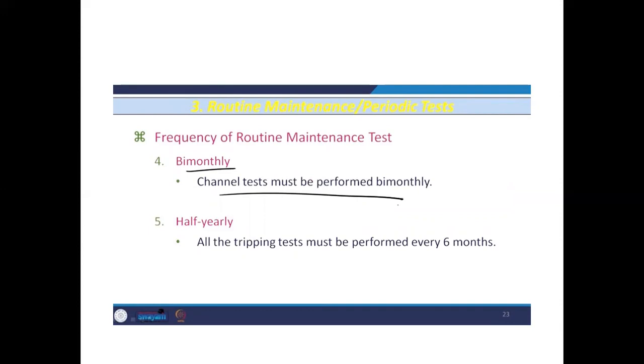Bi-monthly means every 2 months. Channel tests must be performed bi-monthly. Okay, half yearly means after 6 months. All the tripping tests must be performed every 6 months, whether it is tripped on a fault or not. Okay, because there may be some relays and circuit breakers which have not tripped for a very long time, so they should be intentionally tripped so that the mechanism, pneumatic or hydraulic, whatever mechanism is used, is checked for working properly or not.